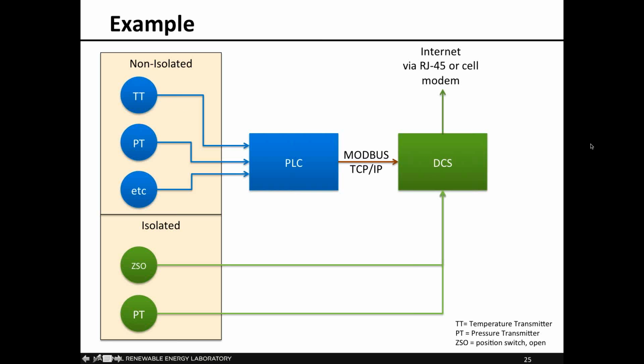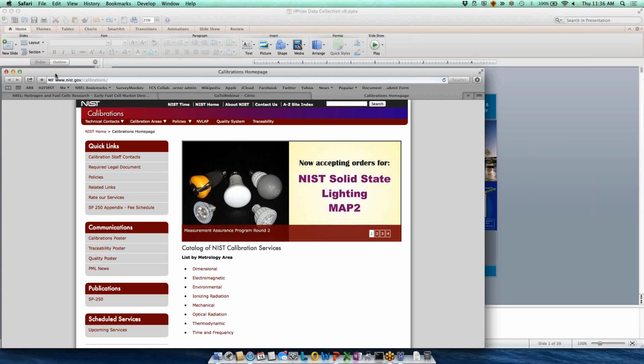The way traceability works, there are national standards for different things: mass, pressure, other things like that. It should load, but it isn't. What happens is sensor manufacturers will take their company's reference standards to NIST and calibrate their reference standard, and then they'll keep their reference standard and use it to calibrate their sensors. Here we go. Yeah, a picture's worth a thousand words.